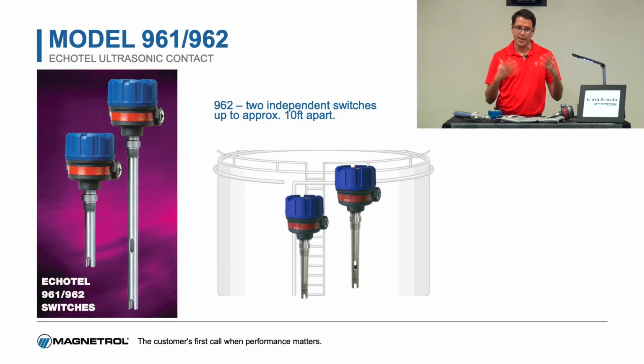if it's not working. So that's a self-diagnostics device, which is kind of a smart device versus the old school mechanical switches that you had to actually go out there and yank a lever to make sure that it's still working. With this device, if it stops working, it will tell you. If the board's shorted, it will tell you that the switch is no longer working and you need to get either a new board or just a new device. So the 961 is the one that you see here on the screen on the left. That is the single point device, high level, low level.